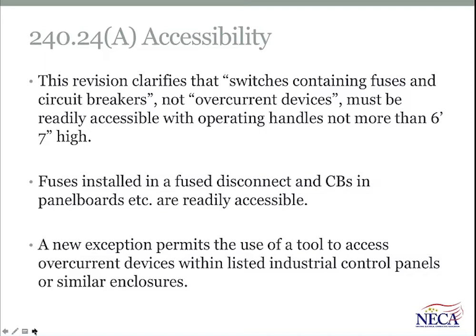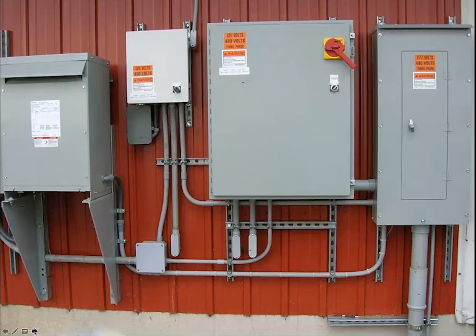And a new exception, and this aligns with the revised definition of the term readily accessible. There's a new exception here that permits the use of a tool to access overcurrent devices within listed industrial control panels. And the photo that you see is typical.